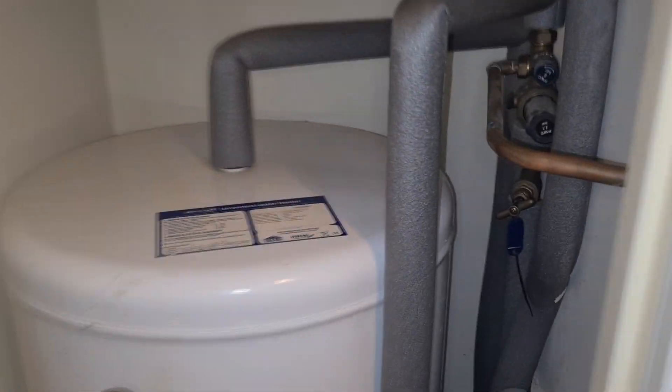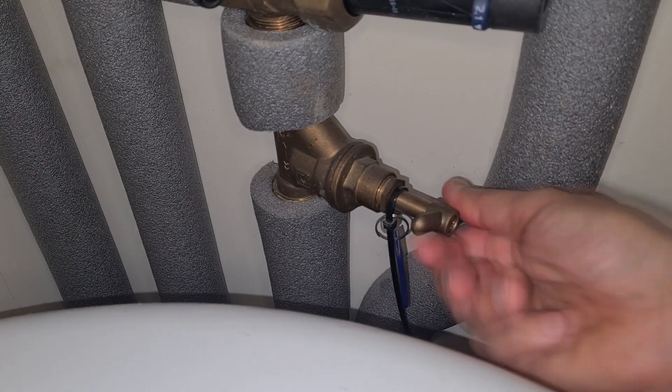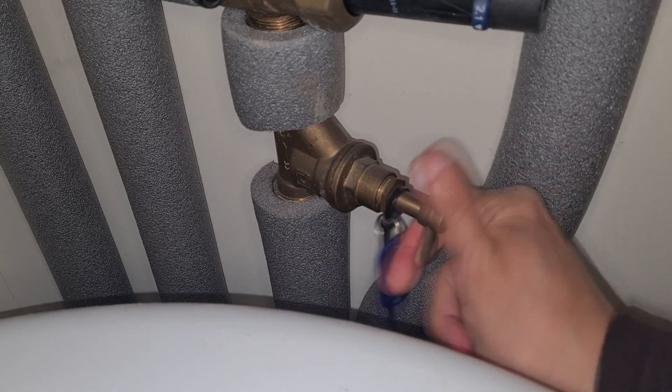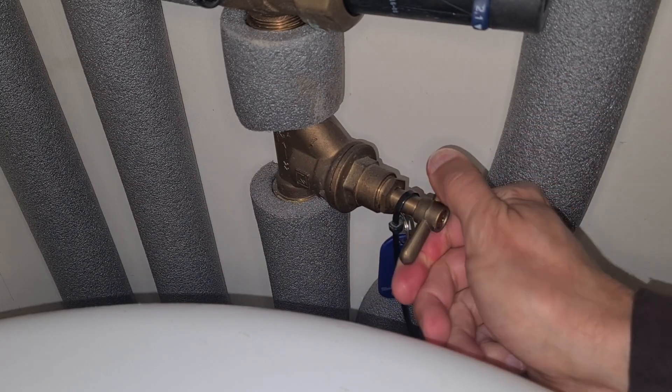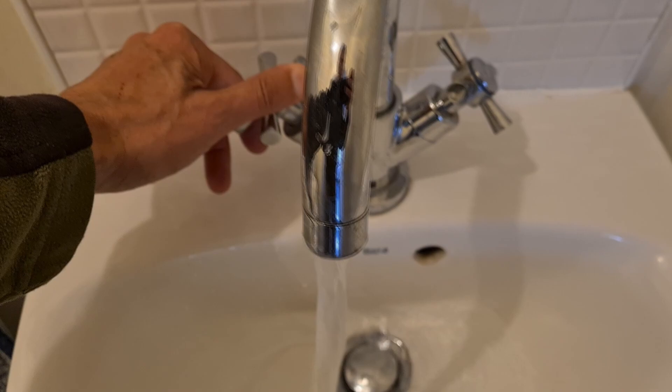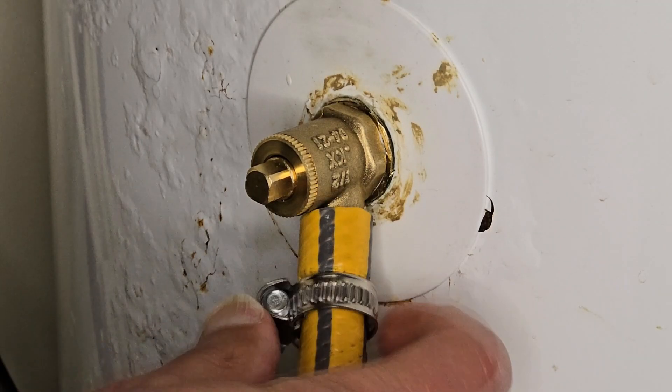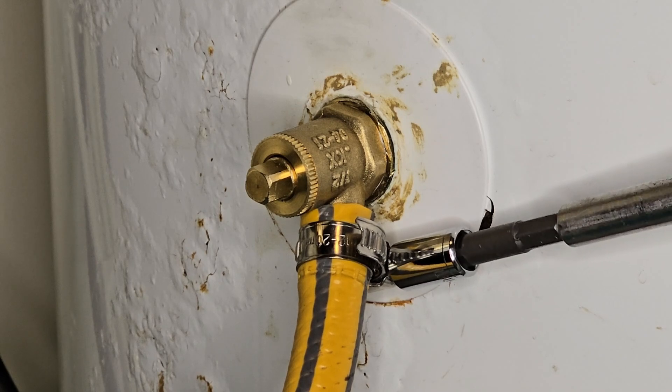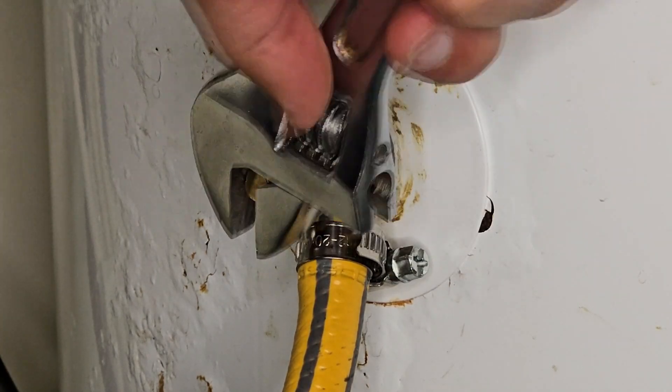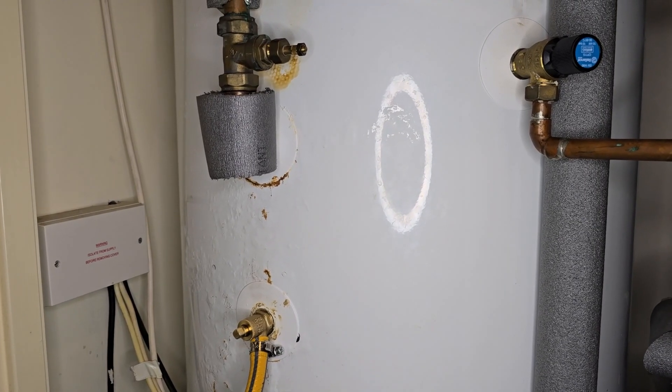The internal air bubble can be easily restored. Turn off the water supply to the cylinder. Open the lowest installed hot water tap. The cylinder needs to be drained to the level of the commissioning valve.